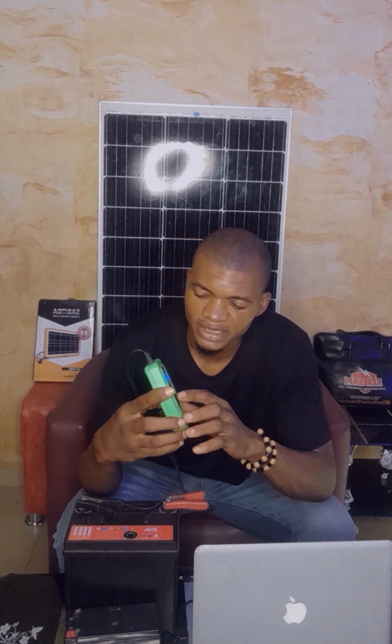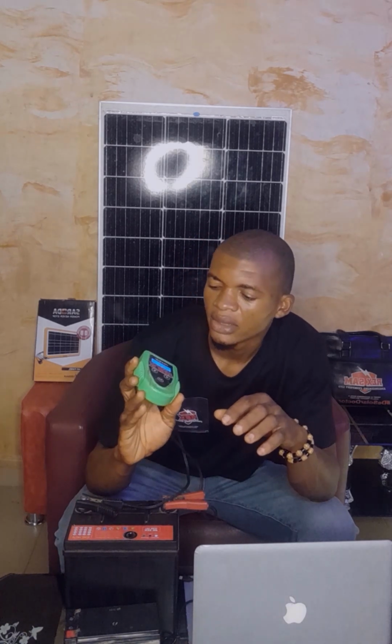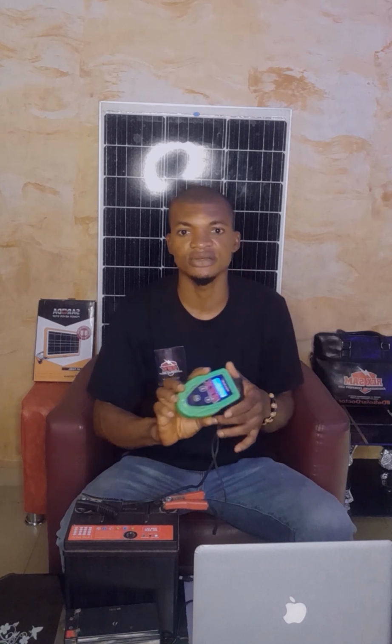Then I will now check the internal resistance. The internal resistance is here, 12.14 milliohms. When you are checking for the one of 200 amps, 220 amps and above, if you are able to get the cycle at between 500 to 1000, the internal resistance should be from 0.4 to 6 milliohms to show you that the battery is at a good state.